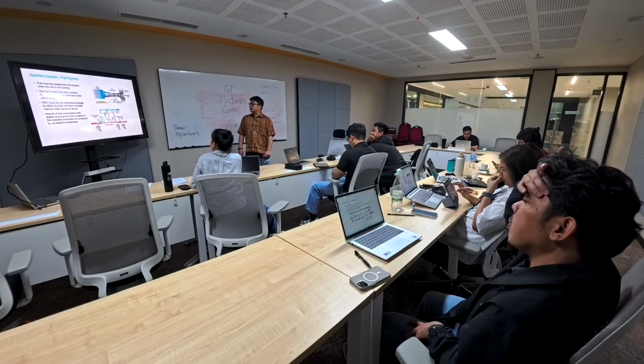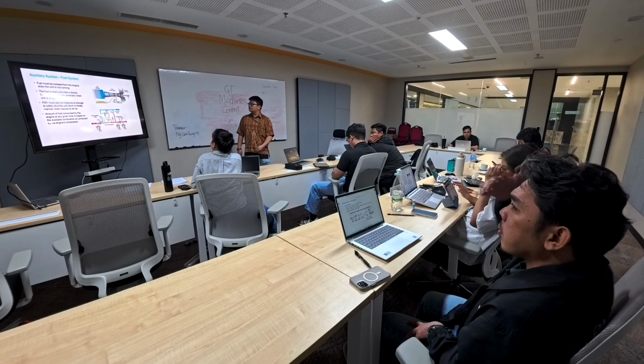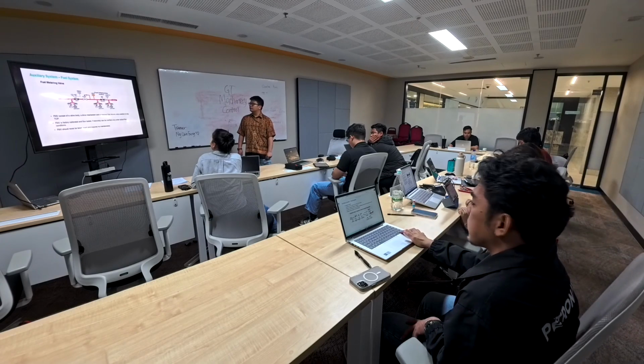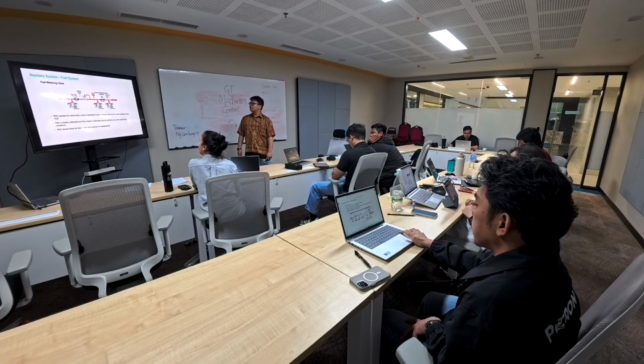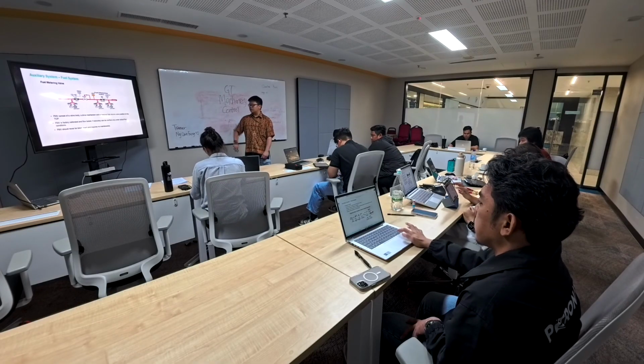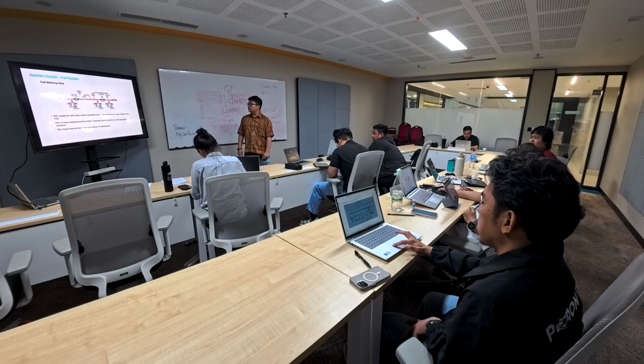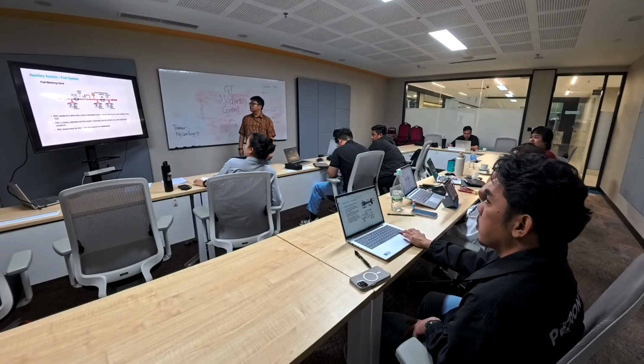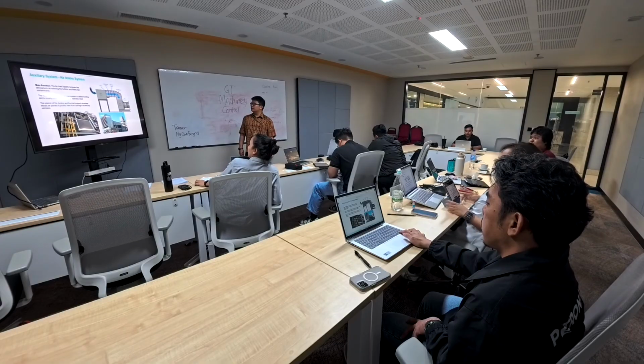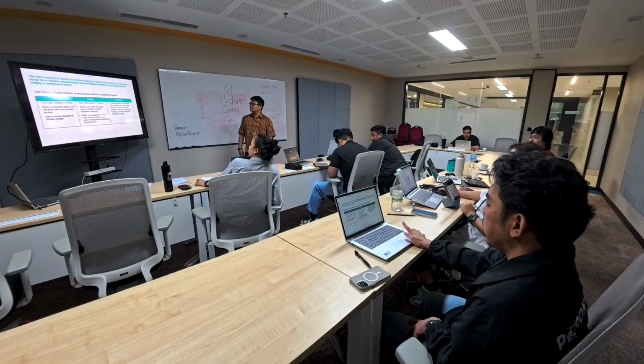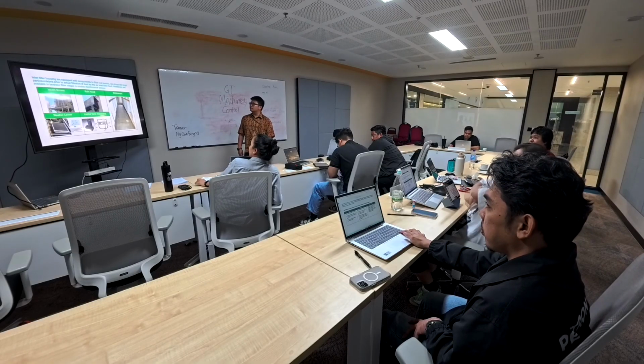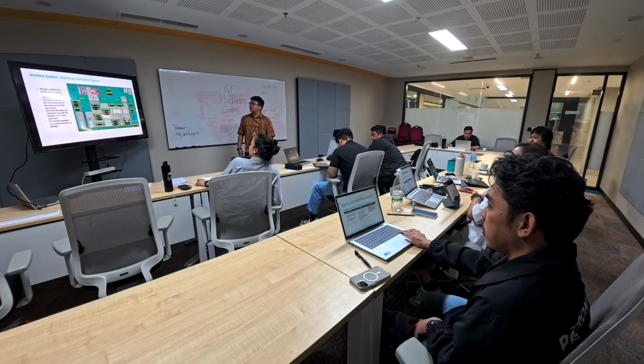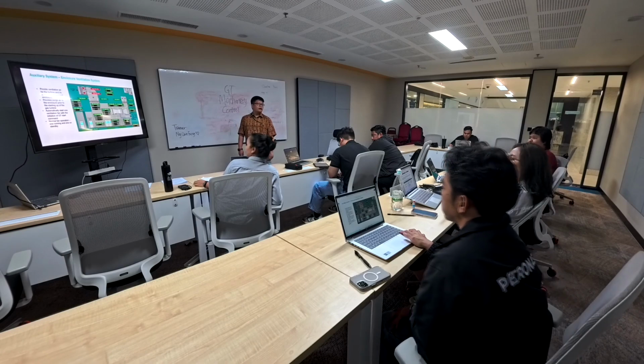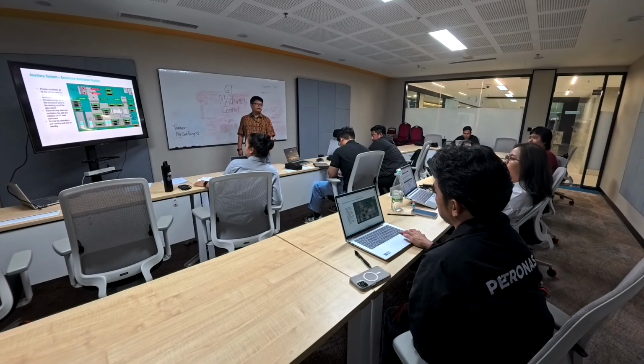Okay, fuel system must be isolated. I mentioned it's responsive. Fuel metering valve: normally now the fuel metering valve is all PECC driven, electronic driven. Intake system, okay, I will skip a bit. Is there anything that you guys want to stop me and ask? You can stop me. Inlet, enclosure ventilation. Enclosure ventilation provides push and pull. Always run 1+1. If you have no choice, you run 2.